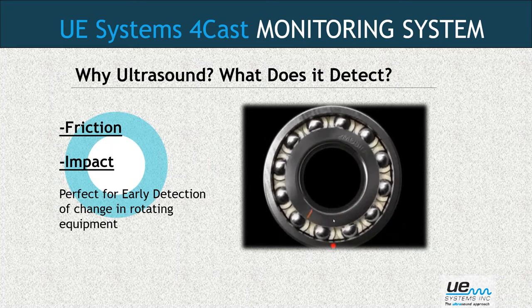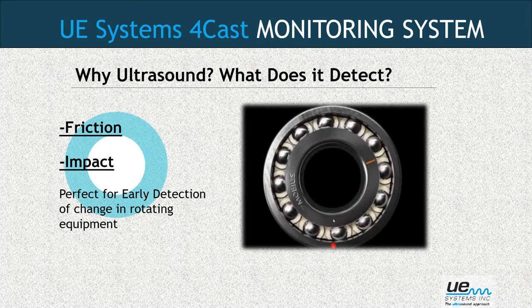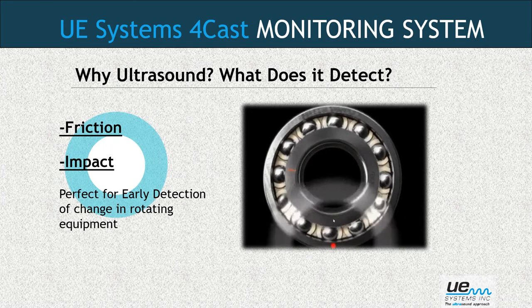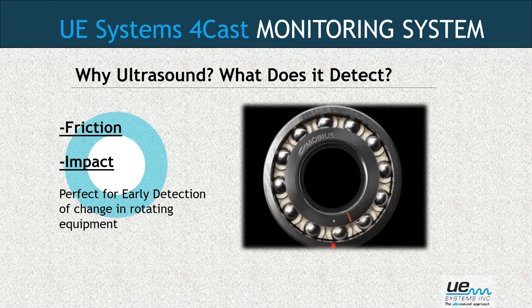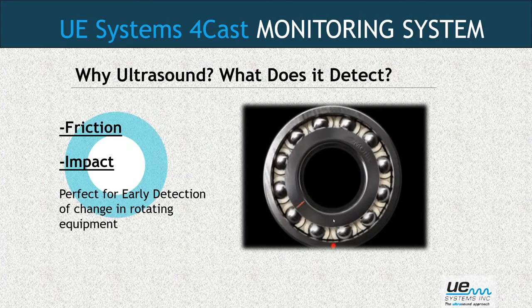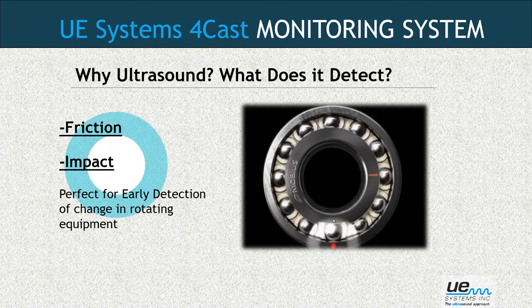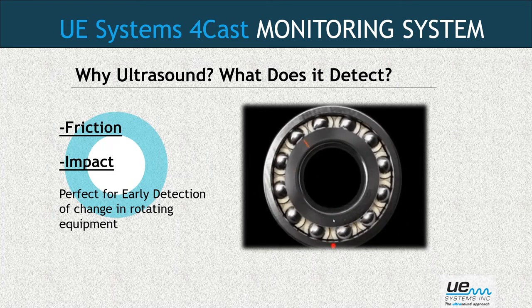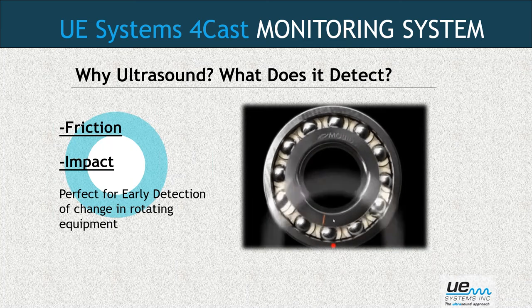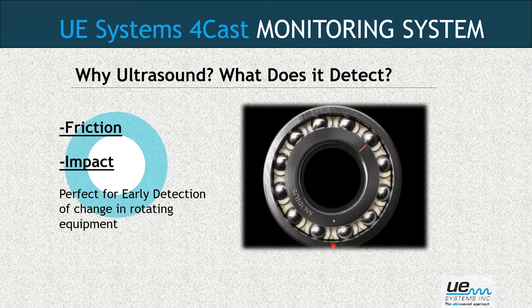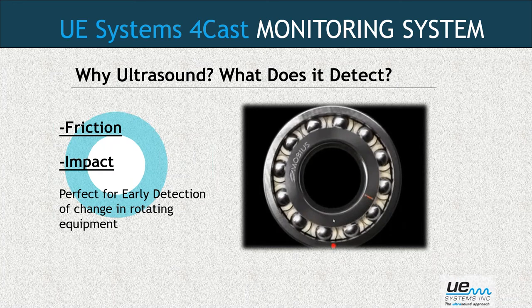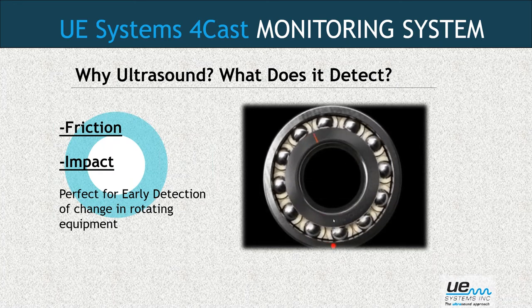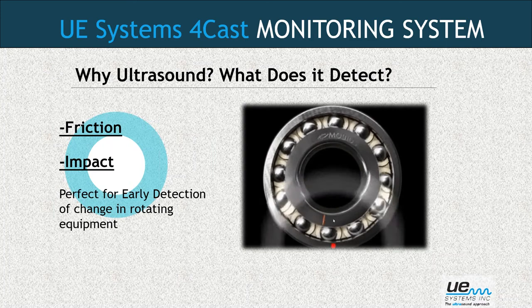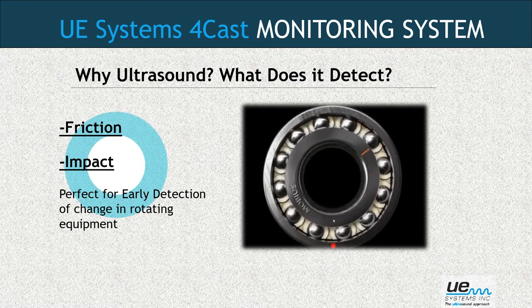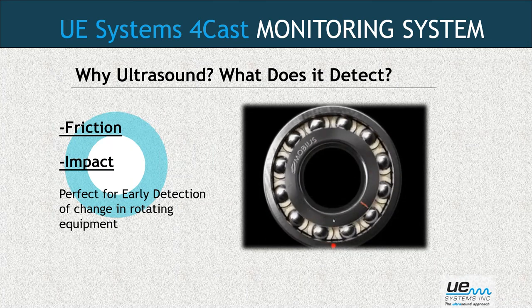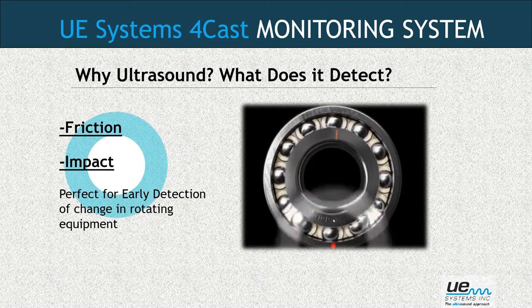So why ultrasound? What does it detect, and why do we use it? Ultrasound picks up two things essentially on rotating or mechanical equipment: friction and impact. It picks up the high frequency sound created from too much or too little friction. Thinking about a bearing, for example, an increase in friction could mean lubrication has broken down, raising the sound level. If we develop a bearing fault - a nick on a race or a flat spot - every time it goes around, it will impact.